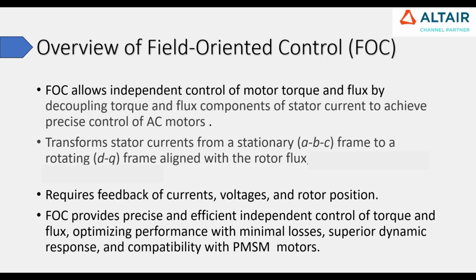Coming to the control topology used for the PMSM motor control, we are using the field oriented control. The FOC here allows independent control of motor torque and flux by decoupling torque and flux components of stator current to achieve precise control of AC motors. So here we will be using the Clark and Park transformations to calculate the VD VQ values. Based on that, we will be calculating the switching frequencies, which will ultimately control the current into the PMSM motor. So this is the basic understanding of FOC control.